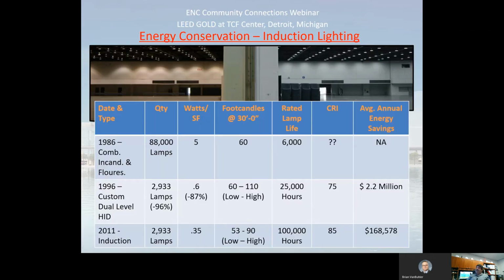Well, the story didn't happen overnight. It took a considerable amount of time for us to get here. Back in '86, our exhibit halls utilized 88,000 lamps at 5 watts per square foot. We didn't have an awful lot of light either at that time. We were only about 60-foot candles, and if we could get 6,000 hours out of a lamp, we were doing very well. Some of them were considerably less, around 2,000 hours. So we were constantly changing lamps or had a terrible burnout rate up in the ceiling.